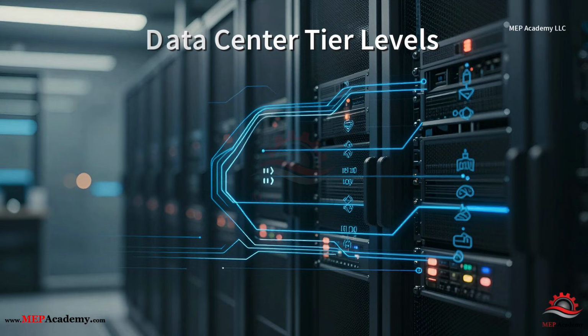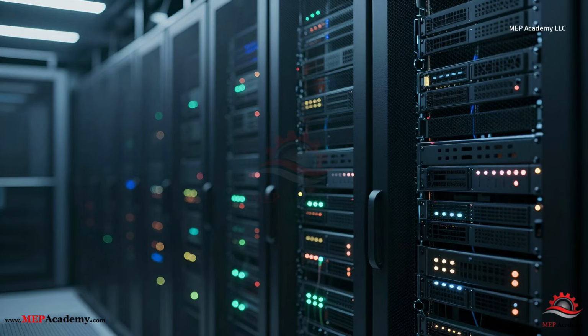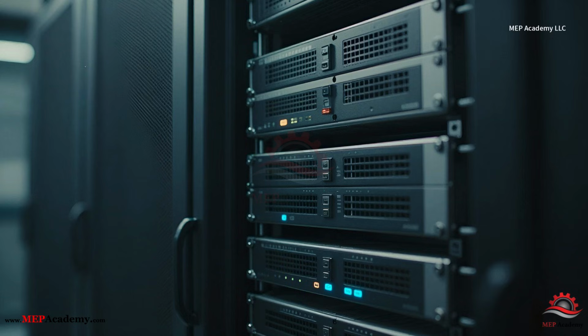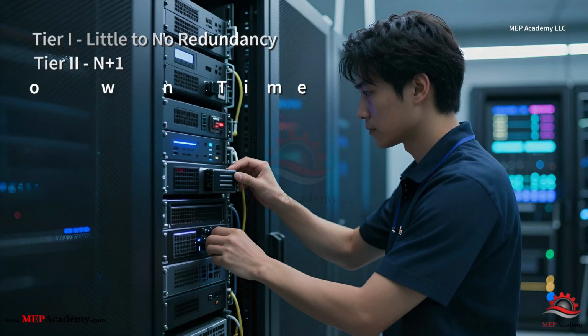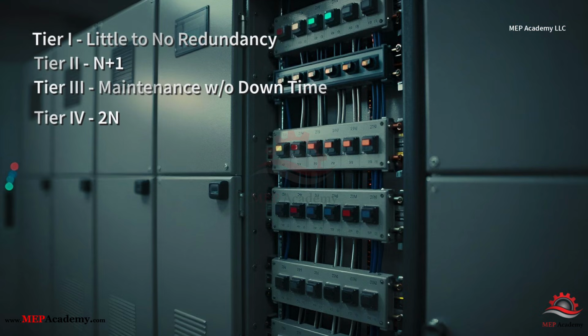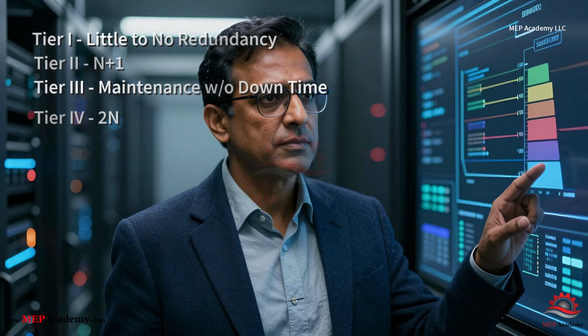Redundancy levels are closely related to data center tier classifications. Higher tier data centers include more redundancy and fault tolerance. For example, Tier 1 facilities typically have little or no redundancy. Tier 2 facilities often include N+1 components. Tier 3 facilities allow maintenance without downtime. Tier 4 facilities use fully fault-tolerant systems such as 2N architectures. These classifications help organizations choose the level of reliability they need.